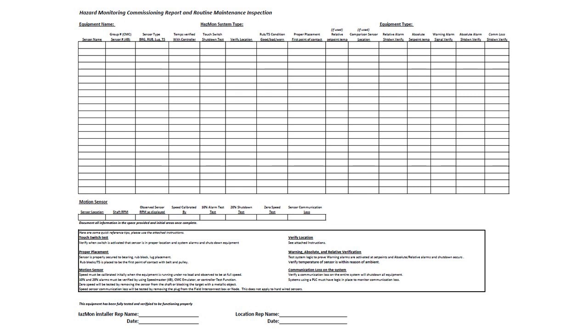If we lose communication, you pull the cord, does it keep reading static temperatures? That happened. So we have this whole commissioning process to make sure it functions as we say before we hand it over to operations, the elevator superintendent, here you go, here's the sheet, we've checked all these parameters and it's good to go.